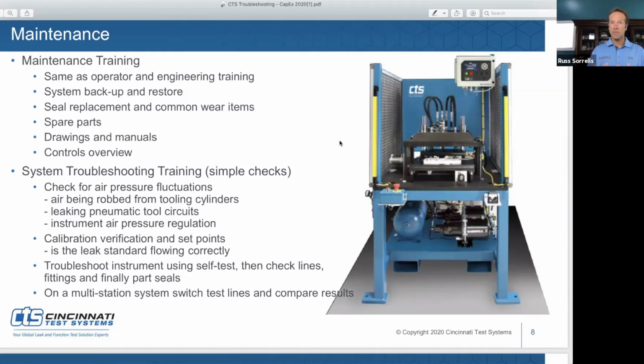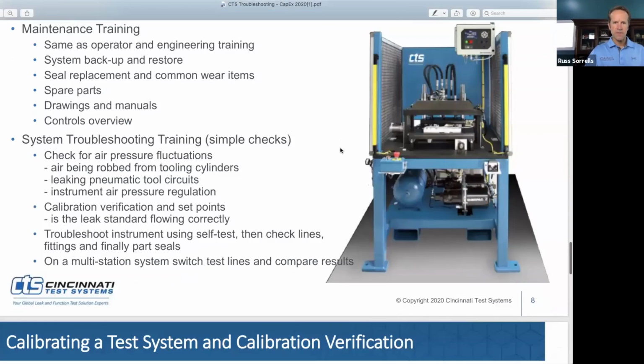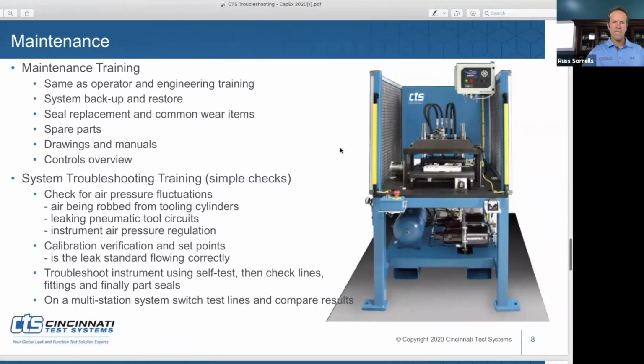So that's the most common problem as it relates to the instrumentation. But another very common issue, I don't know if it's addressed in some of this documentation, is the setting. When operators or customers go to set them up, let's say their target pressure is 20 psi. They set their upper limit to 20.1 psi and their lower limit to 19.9 psi. The instrument is trying to hit that window we've set, which is essentially 0.1 up and 0.1 down. It makes it very difficult.